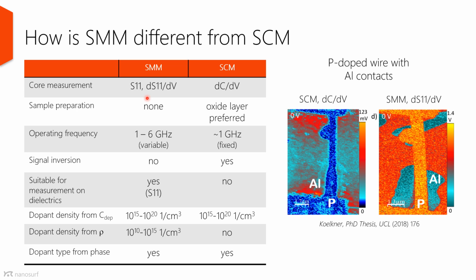The SCM has only the DCDV mode. In terms of sample preparation, the SMM is more forgiving. The SCM works best with the oxide layer. In terms of operating frequency, SMM has variable operating frequency, the SCM is fixed. There is a signal inversion in SCM which does not happen in SMM. In S11 mode, the SMM could be used for measuring the dielectric constant. The SCM cannot do that. In terms of range of the dopant densities, both techniques are pretty similar in the dC/dV or dS11/dV mode, but the S11 mode in SMM could be used for measurements of lower densities. Overall, the SMM is technologically more advanced than the SCM and is clearly a better measurement technique.